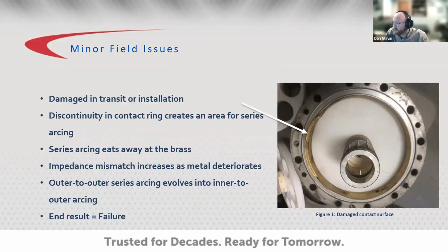Some of these will be more familiar and some of you may have seen many of these and some may never. So this figure 1 shows a damaged and folded contact surface of the transmission line flange on a gas stop barrier. It's likely that this damage may have occurred in transit or during installation. The discontinuity of that folded over contact surface creates a variable that is susceptible to series or continuous arcing from the outer conductor of one piece of transmission line to the outer conductor of the next.